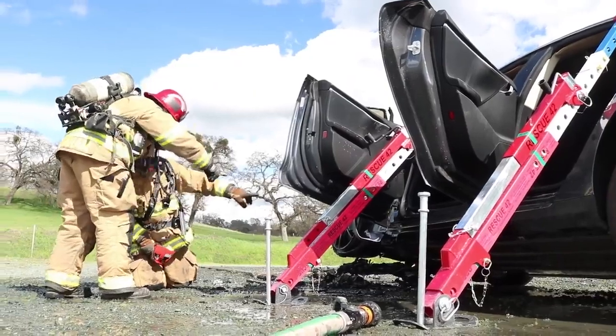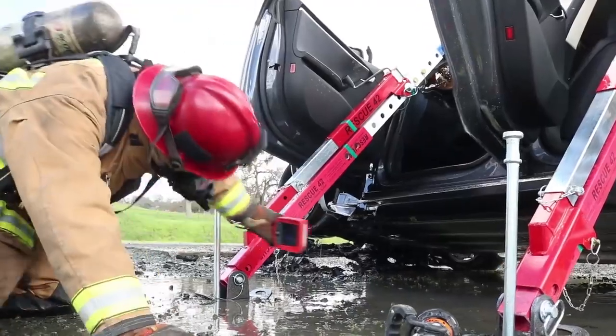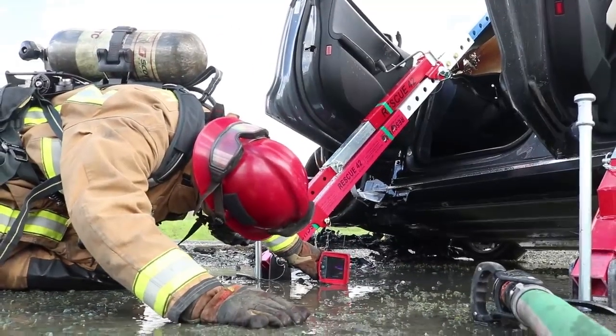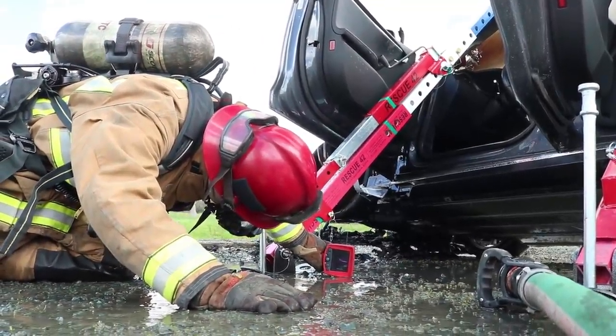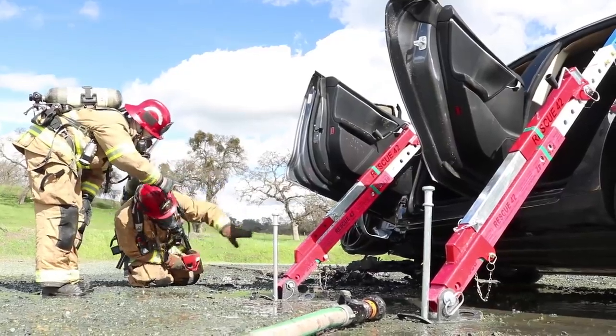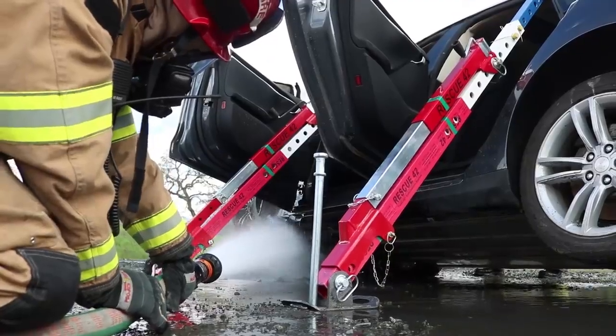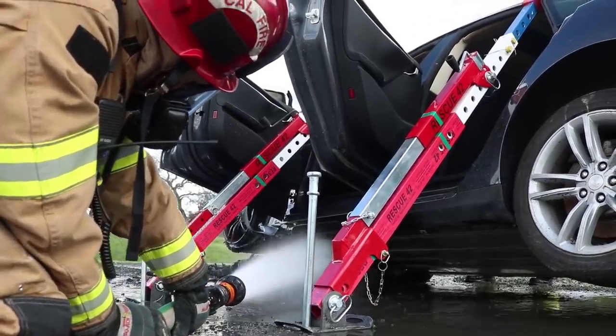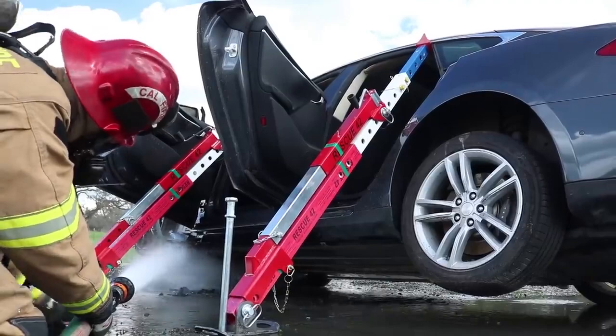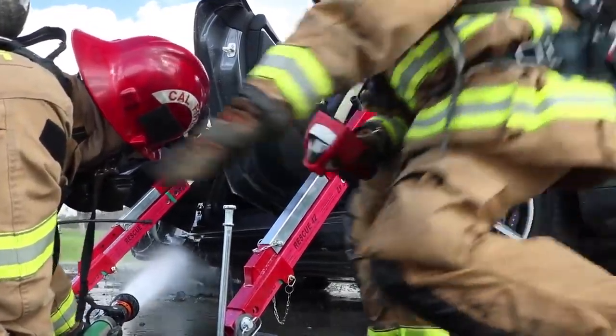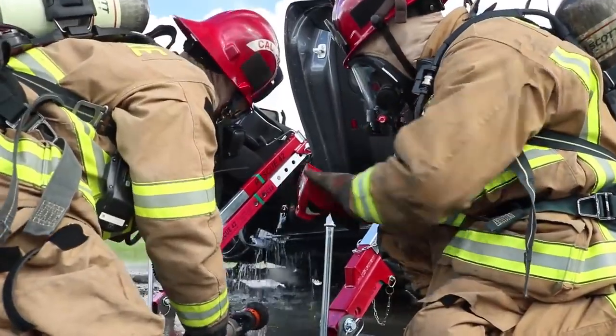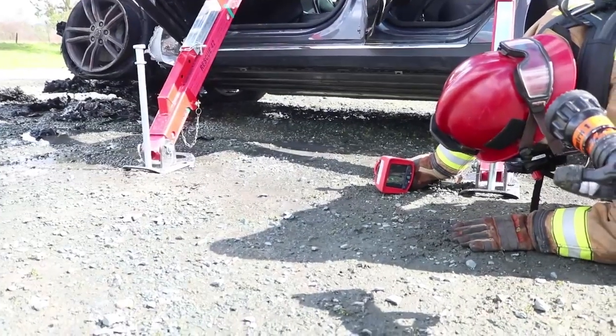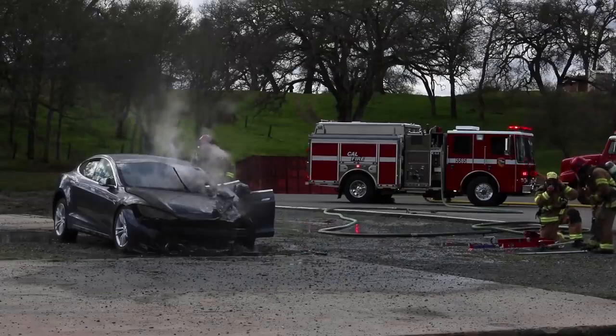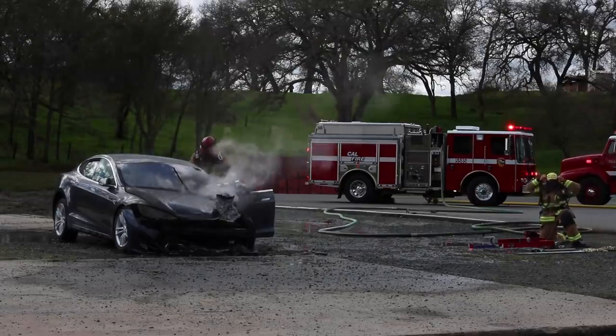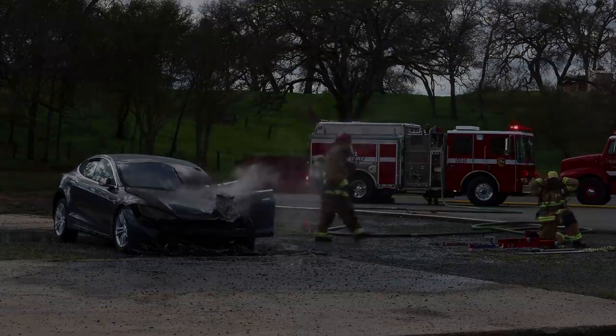The battery case was then checked again after the cooling operation had been stopped for 5 minutes. This time was given to allow any potential heat to transfer from the cells of the battery onto the battery case. The battery case was found to be over 200 degrees Fahrenheit and cooling operations began again. Cooling continued for another 8 minutes until the battery was found to be sufficiently cooled. The vehicle was monitored for 45 minutes and no signs of thermal runaway were detected. The entire operation used approximately 4,000 gallons of water, and the vehicle did not reignite at any point after the testing.